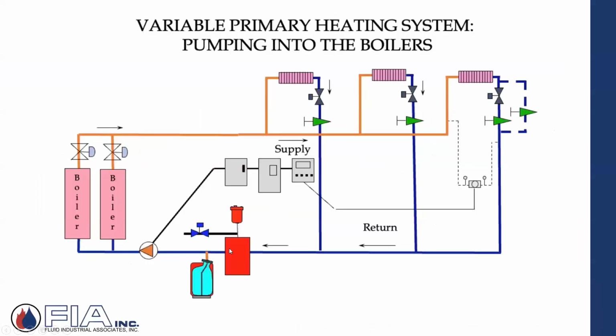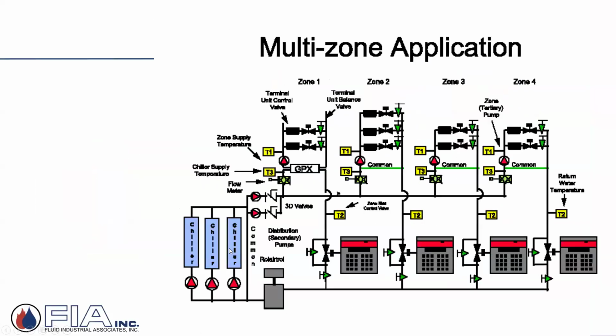speed control. And then a third, I think we touched on it the first week briefly, but this is fairly busy, that would be primary, secondary, tertiary. So I'd have my plant, my chiller plant in this case, perhaps my distribution that's feeding multiple buildings. And then within each building, I have my tertiary pump going to my fan coils or whatever they are, my terminal units within each building on campus perhaps.